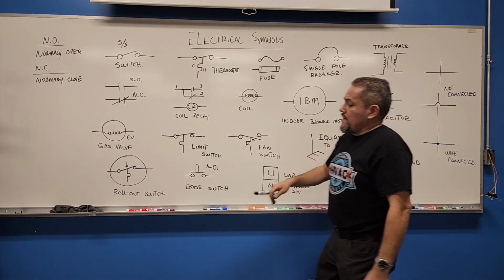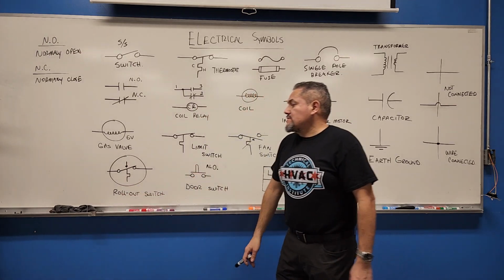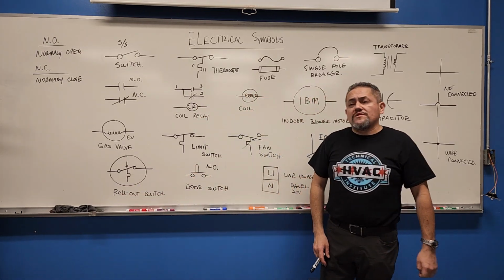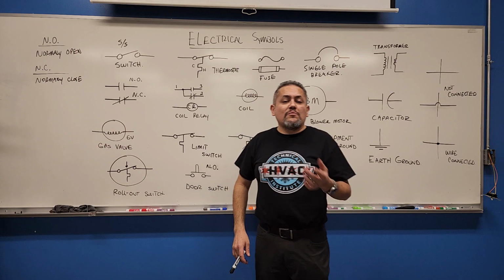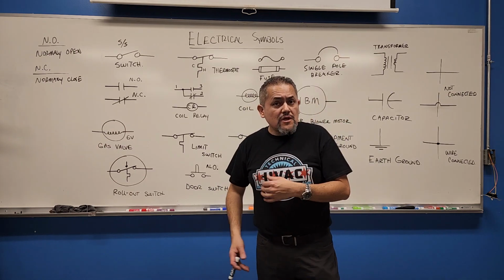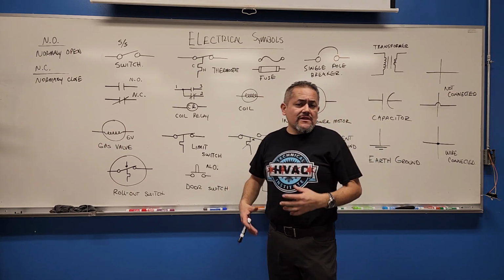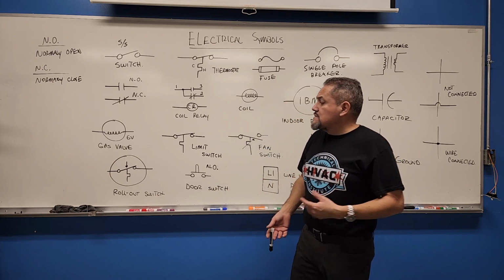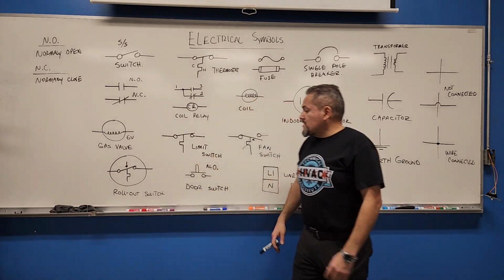Go back to here, and the rollout switch. Right there, this is the rollout switch. This will be a normally closed contact. It only opens if the flame rolls out of the furnace, which happens sometimes if the customer doesn't do maintenance to the furnace. Normally closed contact, rollout switch.